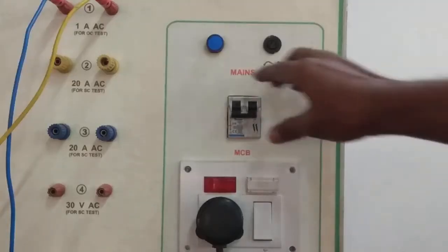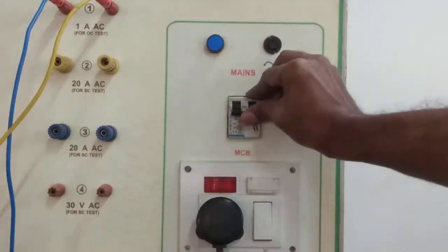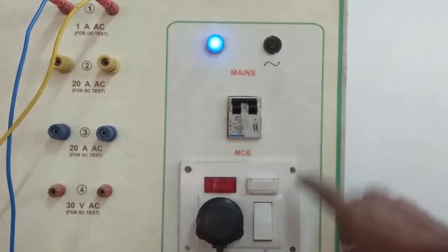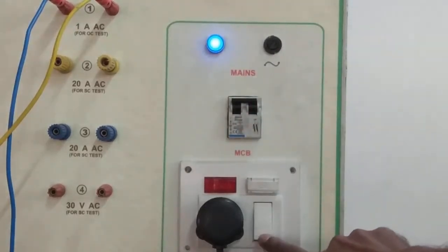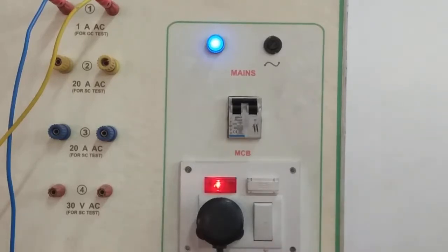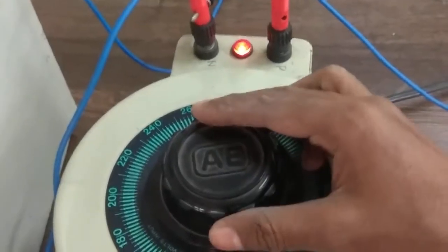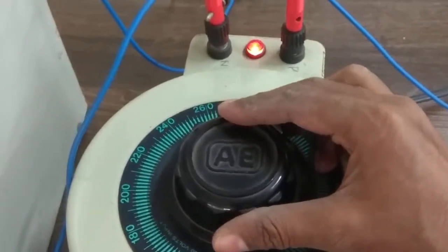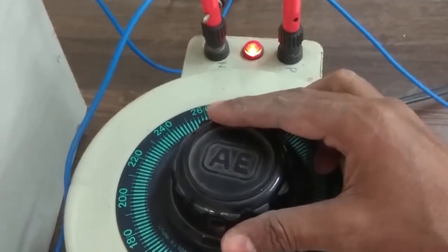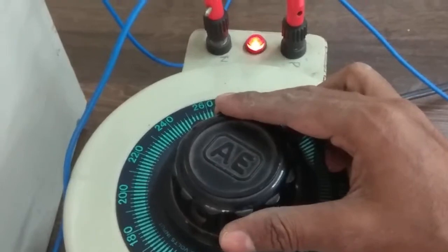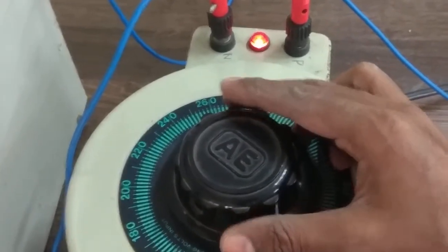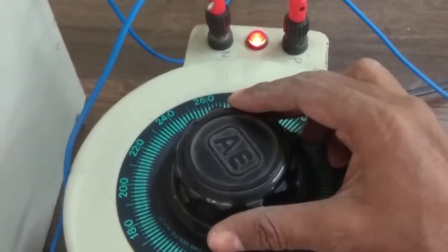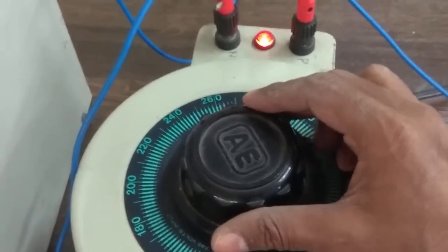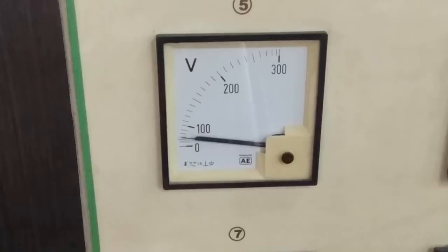Now we will switch on the supply with the help of this MCB, and with the help of this SP switch we will give the supply to the variac. Now we will slowly increase the variac by adjusting its knob and bring the voltage to the rated LV voltage, that means 115 volts. We will bring the voltage to 115.